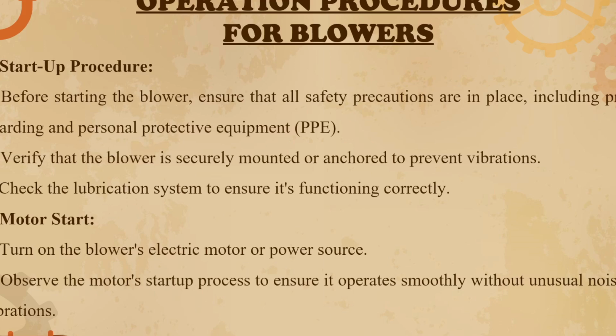So this slide will discuss the operation procedure of blowers. First procedure is the startup procedure. Before starting the blower, ensure that all safety precautions are in place, including proper guarding and personal protective equipment. Verify that the blower is securely mounted or anchored to prevent vibrations. Then check also the lubrication system to ensure it is functioning correctly.